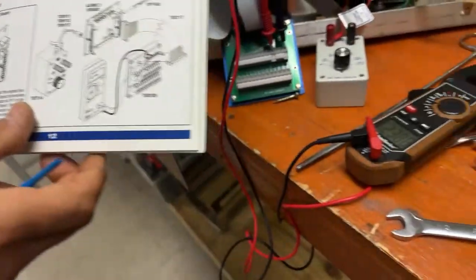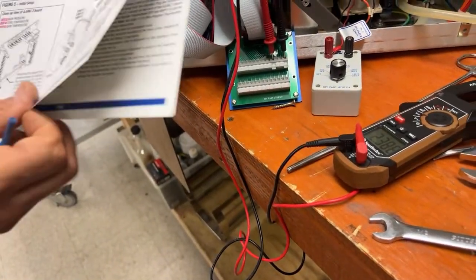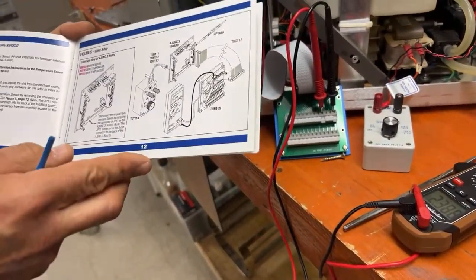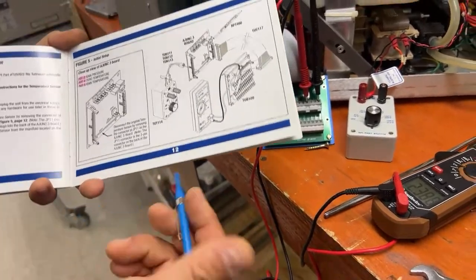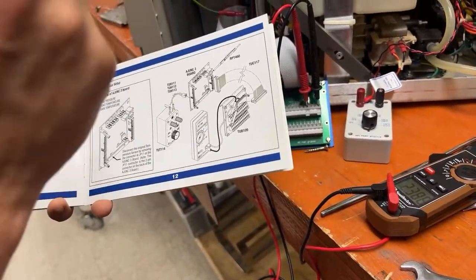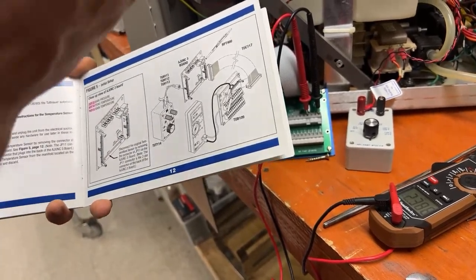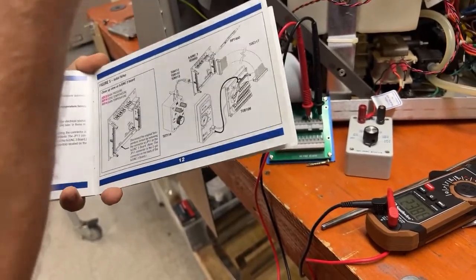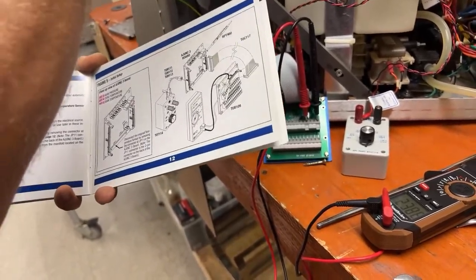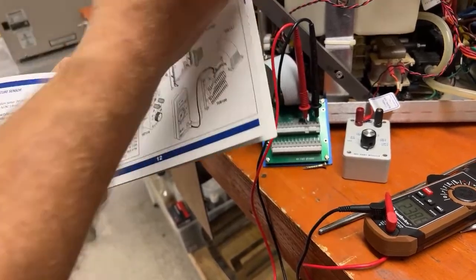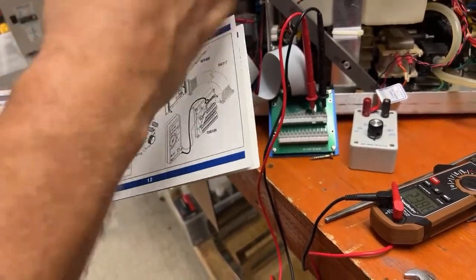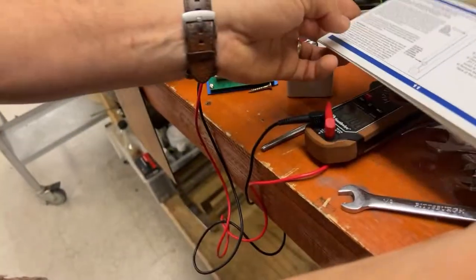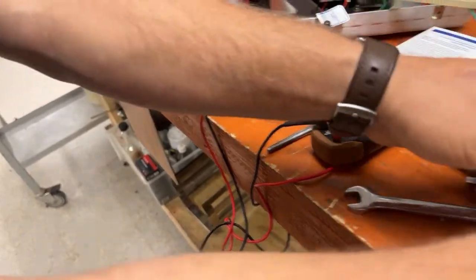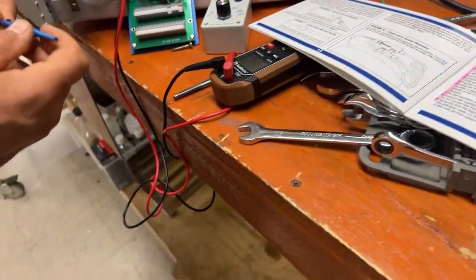All right, and that's the gain temperature. So we did the 0 temperature, now we're doing the gain. Gain is a function of, if you have a sensor that has a high level, 0 is telling it what the floor is, and then gain is telling it what the correct position is at a higher level. Between the gain and 0, that's how a machine knows where it's at in the middle. So just keep in mind that these affect one another. So we're going to adjust that pot 5 for 2.385.